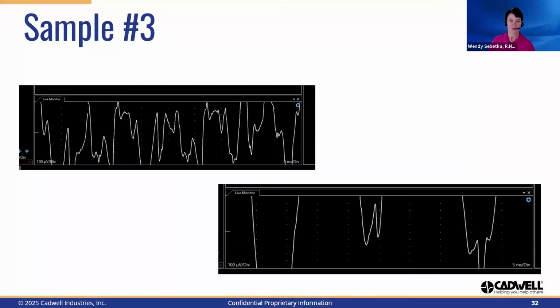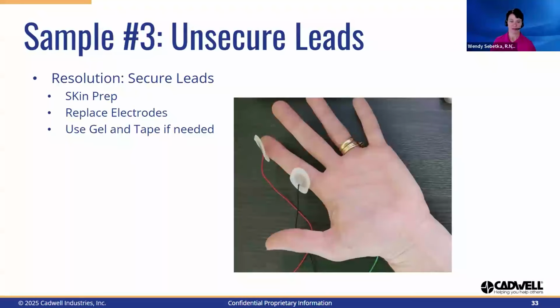The third sample was a new issue that started after successfully completing 5 previous studies that day without issue. I make note of the excessive unexpected deviations from baseline, the disorganization, and possibly some spiky components. With the information I have, I can't feel comfortable narrowing the source down to either a non-physiological or physiological origin at this time. So I performed the previously discussed troubleshooting techniques, starting with the easiest, which is electrode and patient management. Patient and electrode management techniques were performed, and it was noted that there was lotion on the patient's skin that was causing the disposable electrodes to not adhere securely. Alcohol was used to prep the skin to remove the lotion, and tape and gel was used to secure the electrodes. Electrical noise was resolved, and adequate waveform was able to be obtained successfully.